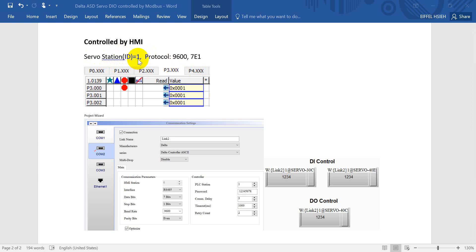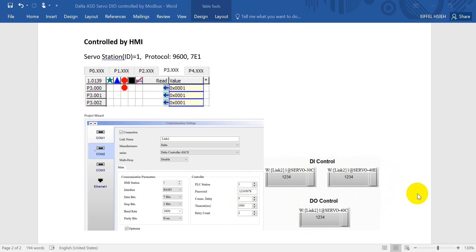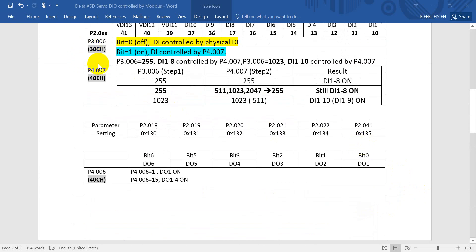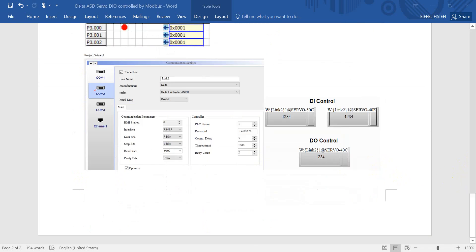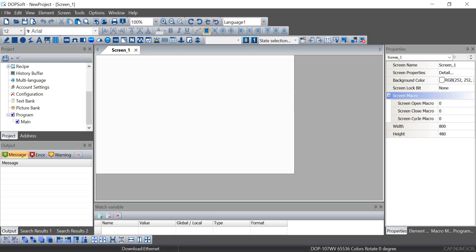Then I will show you the HMI setting. In this example, I use the servo station ID as 1 and the protocol is 9600 baud at 7E1. So that's why here we select 7E1 at 9600. For the digital input, we use P3-006 and P4-007, and this is the corresponding Modbus address. The Modbus addresses are 3-0C, 4-0E, and 4-0C. So then we create the numeric entry for Modbus control.